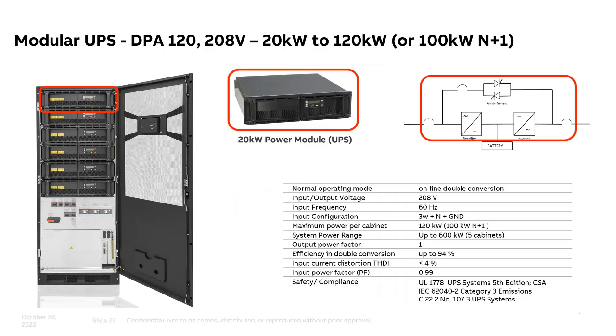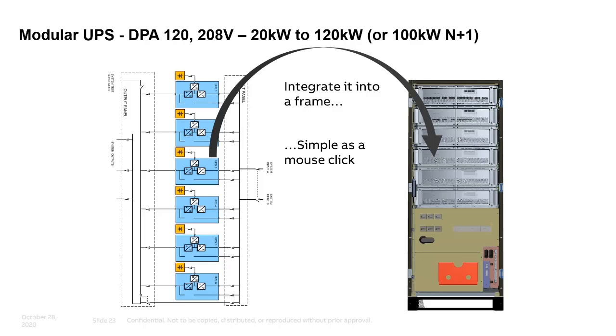In that frame you can create a modular UPS. So, just going quickly over the ABB offering, at the 208 volt, that's based on that same 20 kW module I just showed. There's one frame that will house up to 6 of them, so it'll support up to 120 kW. That's what it's rated for. But obviously a customer can start with 1 or 2 and then add more as needed. And ultimately, because it's a decentralized or distributed configuration, it'll support a true 100 kW N+1, because it's essentially 6 small UPSs operating in parallel. This is another simpler way of showing the single line of what that UPS looks like: 6 small UPSs in parallel in one frame.